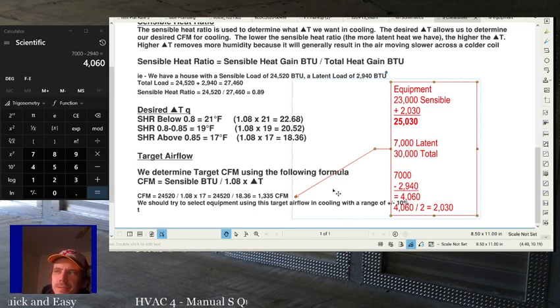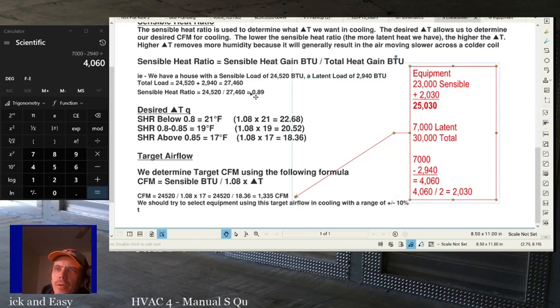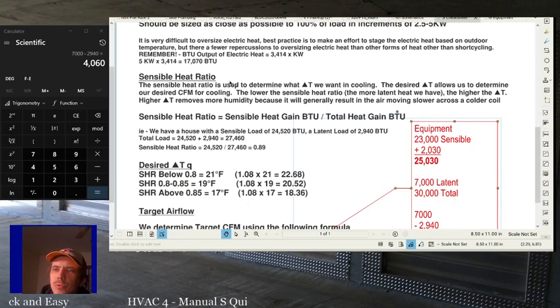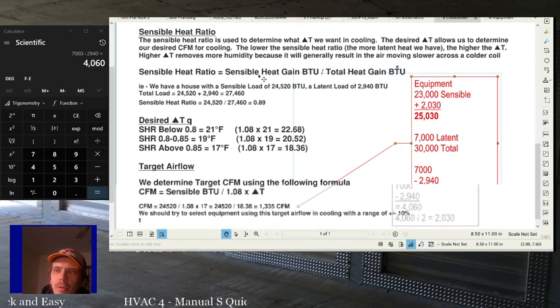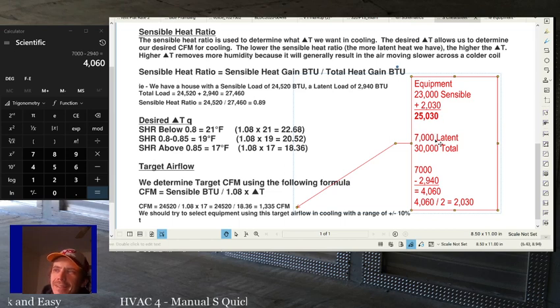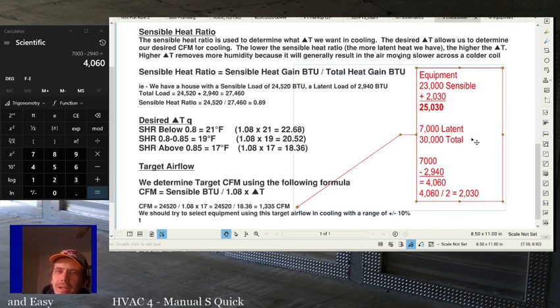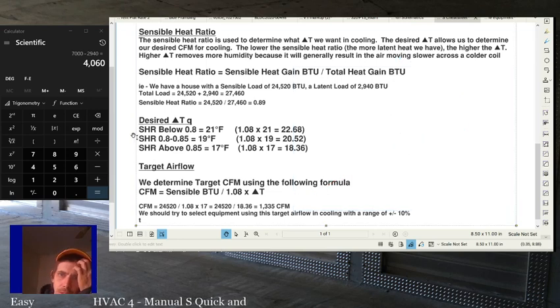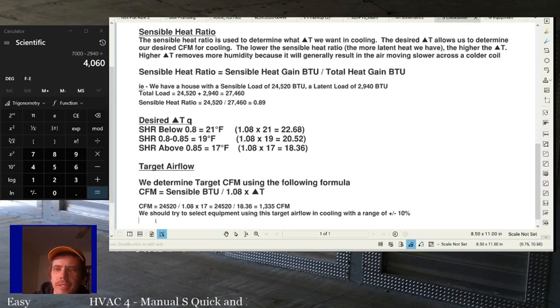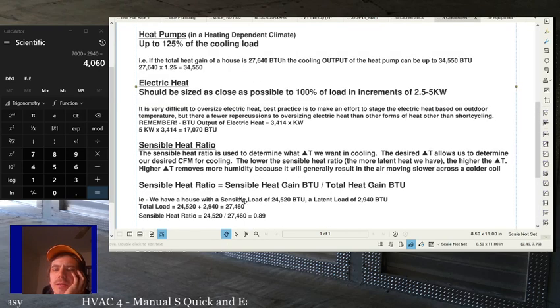If that didn't make sense, just remember half of excess latent can be added to sensible. And if you're in a pinch where it seems like none of your equipment works, come back and watch this until you get it, and use that to your advantage, because there are times where you're in these in-between loads and it seems like nothing is going to work. But if you remember that you can add half of excess latent to your total, you'll get there. All right, so that's your example for that. Just try to keep that in mind. Other than that, it's not that important. It's semi-rare that you actually have to take that rule into account.